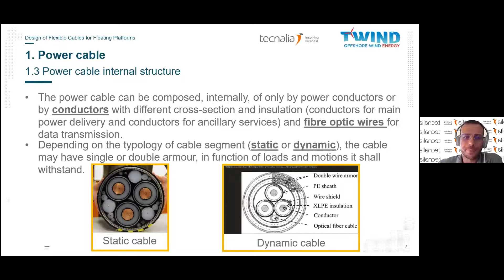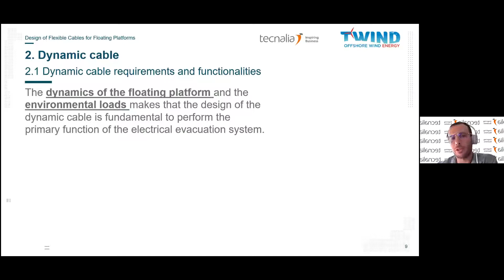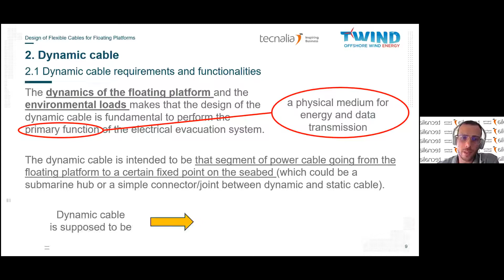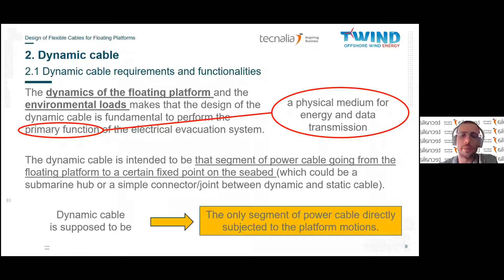And now let's talk about the dynamic cable. Dynamic cables tend to be the segment of the power cable going directly from the floating platform to the seabed. That could be a simple point fixed on the seabed, or a hub, or a connector that normally is connected to the static cable. So the dynamics of the floating platform and the environmental loads make the design of the dynamic cable fundamental to perform the primary function of the electrical evacuation system. That is, as I said before, to be a physical medium for energy and data transmission. The dynamic cable is the only segment of the power cable directly subjected to the platform motions. So that's why it shall be treated differently from the static cable.